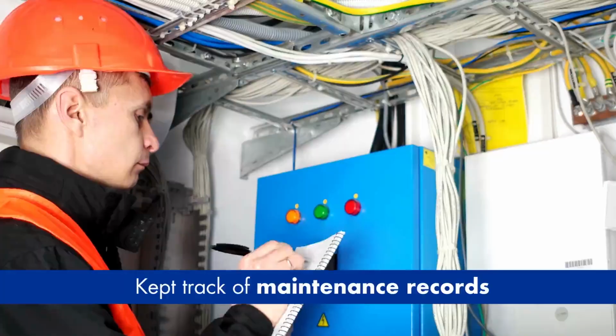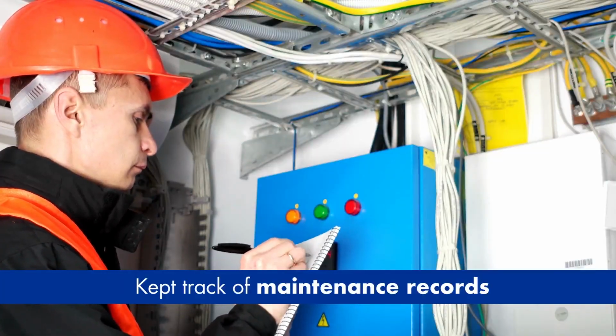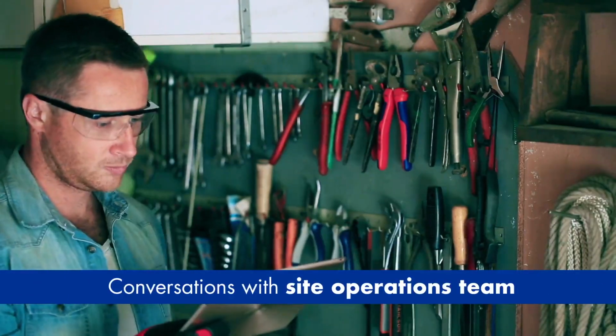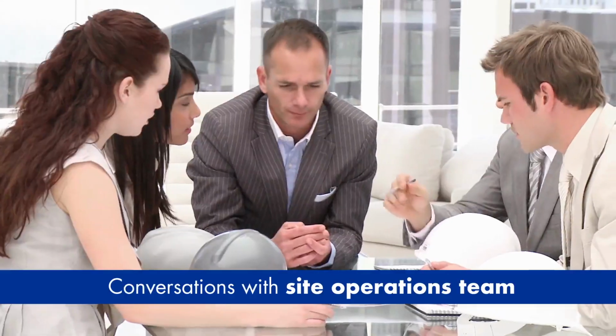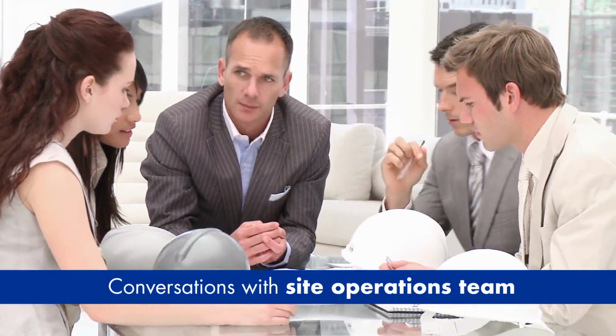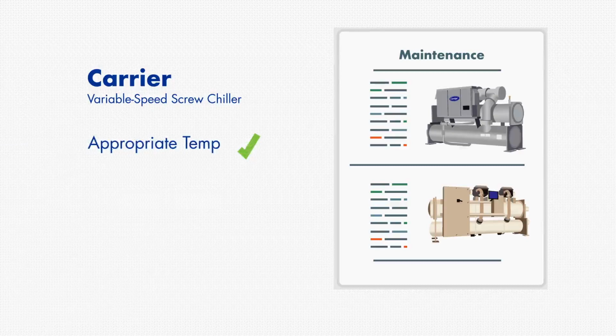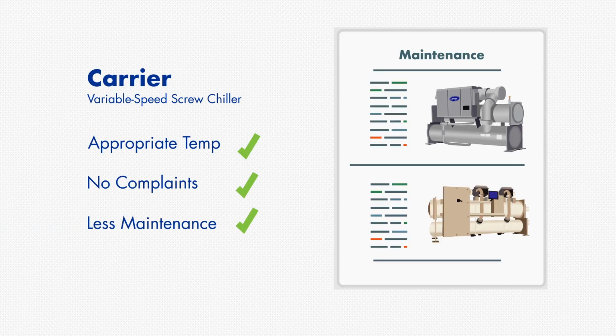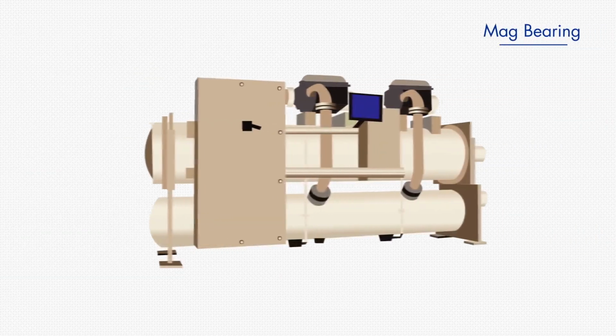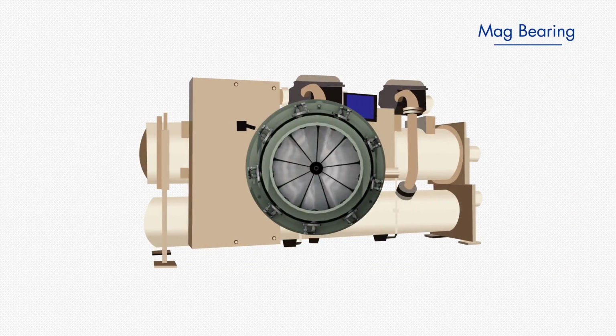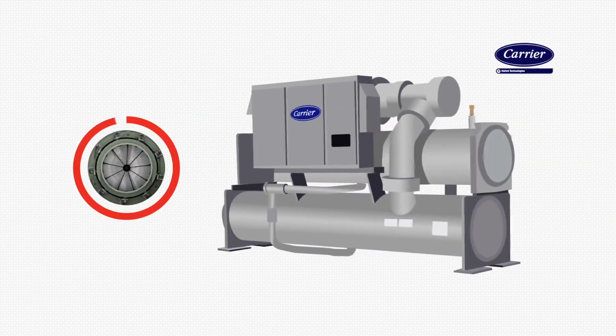The Proving Ground study also kept track of maintenance records and ongoing conversations with the site operations team to gather their overall impressions of the two units. While both units provided appropriate temperatures and operators received no complaints related to comfort, the Carrier chiller required less unscheduled maintenance than the mag-bearing unit. The mag-bearing chiller required repair of mechanical unloaders. The Carrier chiller technology does not use mechanical unloaders, removing this source of inefficiency and potential mode of failure.